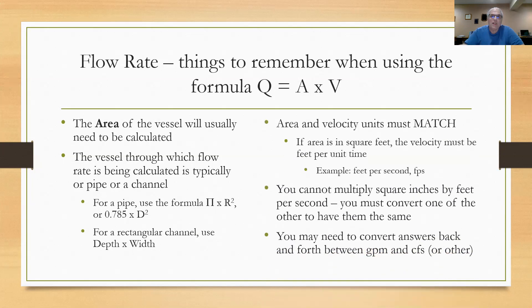Another thing to remember is that area and velocity units must match. If area is in square feet, the velocity must be feet per unit time, like feet per second or feet per minute. You cannot multiply square inches by feet per second - you must convert one of them to have them be the same. You may need to convert between gallons per minute and cubic feet per second using a constant.